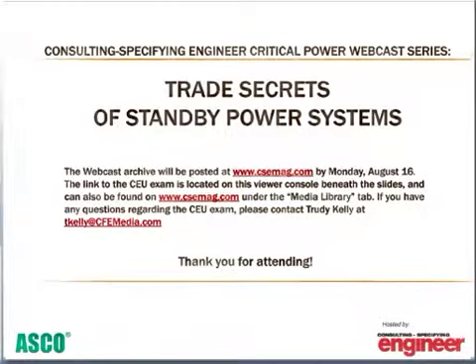Well, I'm not necessarily suggesting them. Many clients, when you get into the large sizes, say 4,000 amp, you can provide your transfer pair via the switchgear with 4,000 amp breakers, or have a separate large automatic transfer switch. So certainly the less expensive means of providing a transfer is to provide a transfer pair for your breakers.